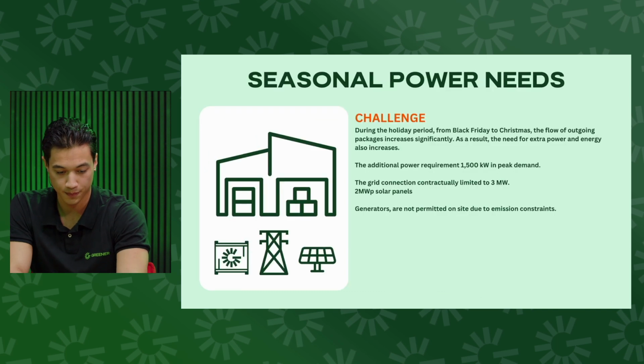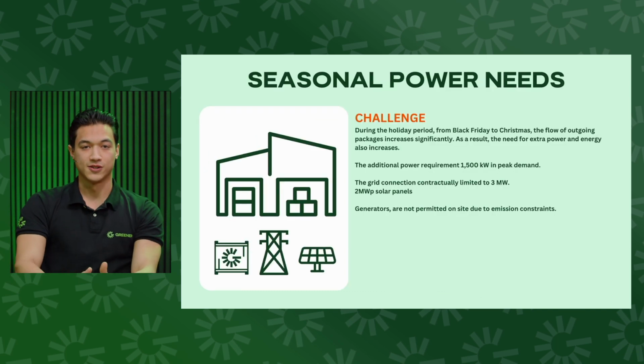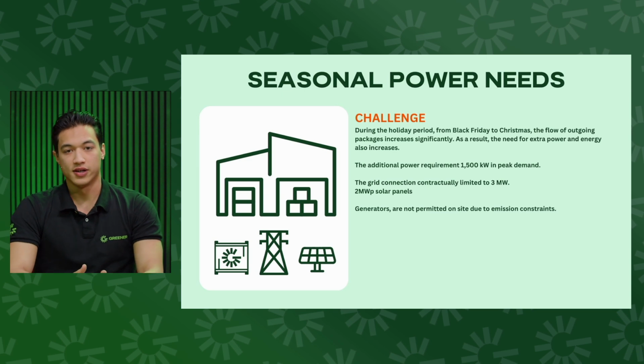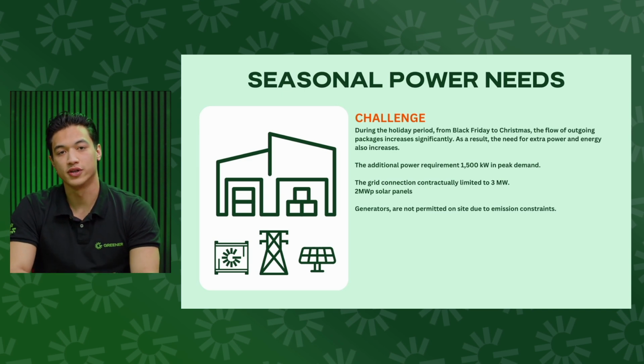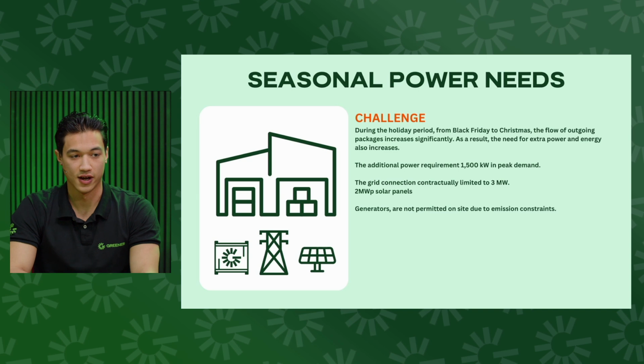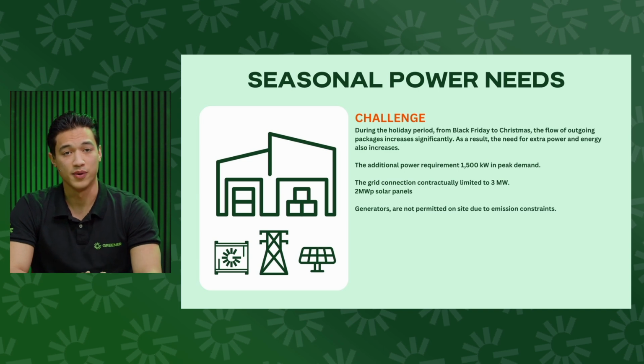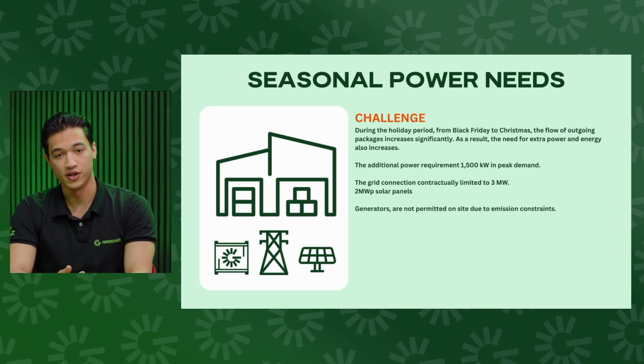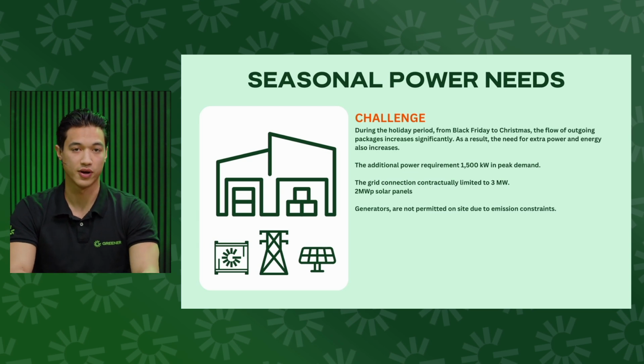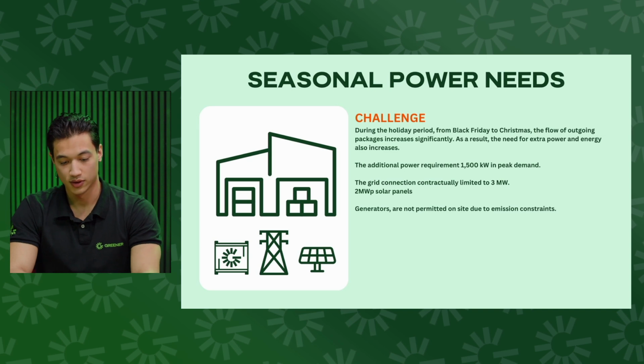All right, now the case. We've got a customer that delivers packaging. During the holiday season with Christmas, a lot of people order presents for each other, and our customer really needed additional power to handle all these packages. The only issue is they only have a grid connection of 3 megawatts, and they needed around an additional 1500 kilowatts, so 1.5 megawatts.